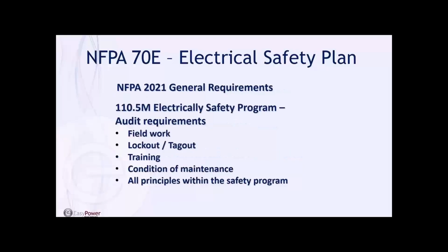That's our take when we focus on writing the electrical safety program within the structure we put forth. The last element of our Article 110.5 survey is that your electrical safety plan also needs audits or audit programs. Ultimately, when you look at what should be audited, in a broad sense, it should be everything. One of the key elements in the electrical safety audit reference is something called the fieldwork audit.